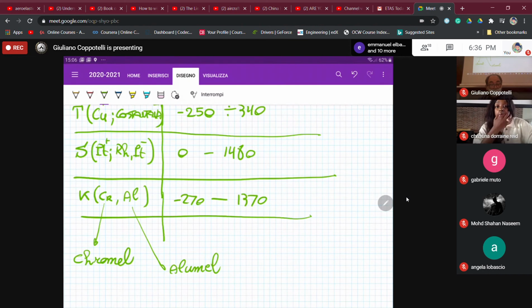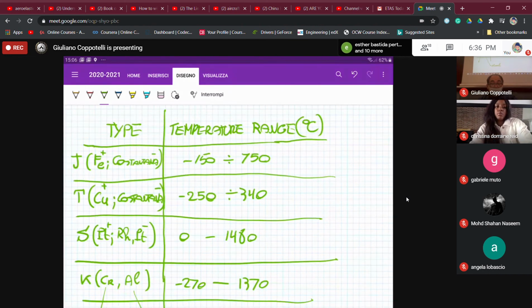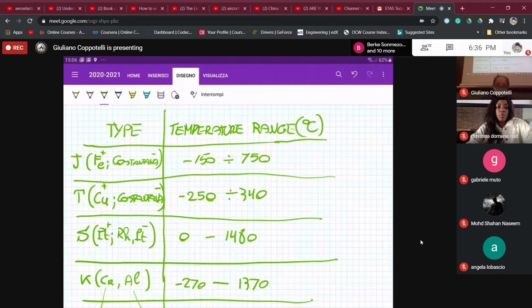So we have different operating ranges in terms of temperature, and different material couplings, that is different thermocouple types. The way we operate the thermocouple is by setting one junction at a known temperature, the cold junction, and the other at the unknown temperature, the hot junction. According to the different materials and temperature ranges, we have a variety of sensitivities, so it depends on the usage needed to select the appropriate thermocouple.